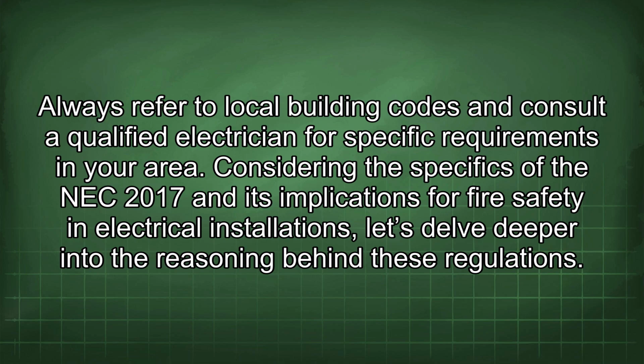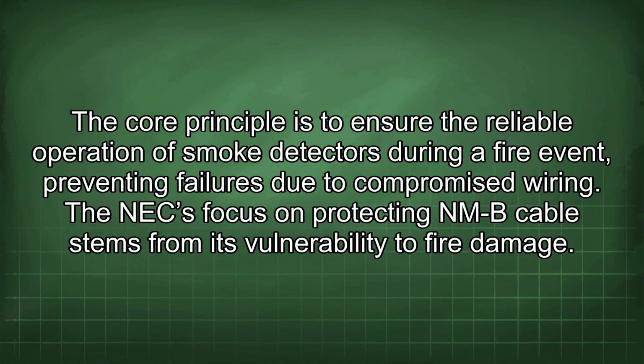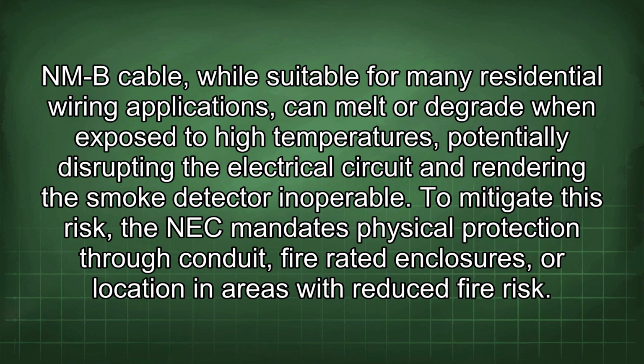Considering the specifics of the NEC 2017 and its implications for fire safety in electrical installations, let's delve deeper into the reasoning behind these regulations. The core principle is to ensure the reliable operation of smoke detectors during a fire event, preventing failures due to compromised wiring. The NEC focus on protecting NMB cable stems from its vulnerability to fire damage. NMB cable, while suitable for many residential wiring applications, can melt or degrade when exposed to high temperatures, potentially disrupting the electrical circuit and rendering the smoke detector inoperable.